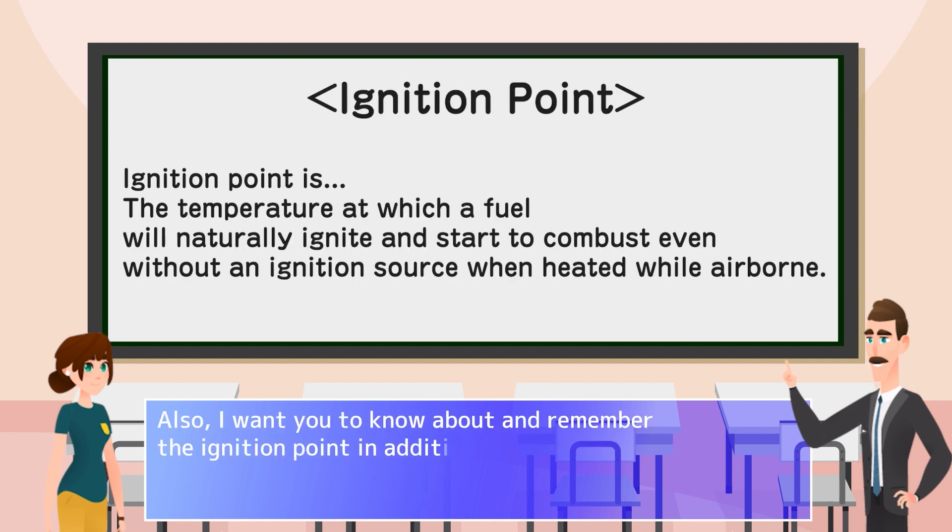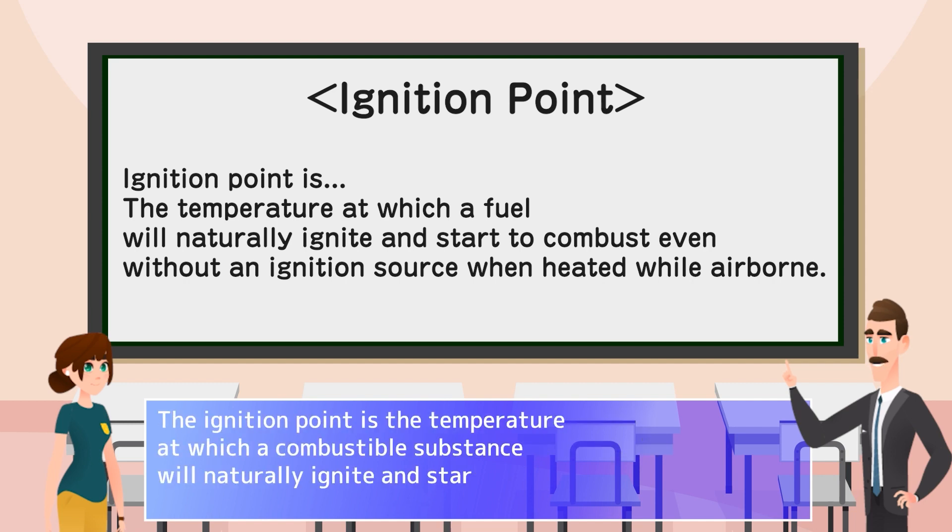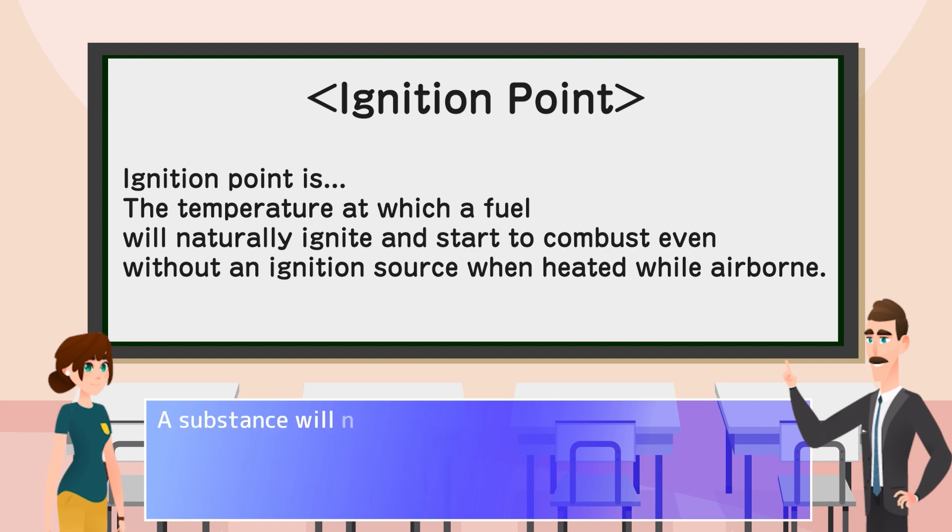Also, I want you to know about and remember the ignition point in addition to the flash point. The ignition point is the temperature at which a combustible substance will naturally ignite and start to combust when heated while airborne. A substance will naturally combust if the temperature goes above the ignition point, so you can't measure its concentration in an environment that is hotter than the ignition point.